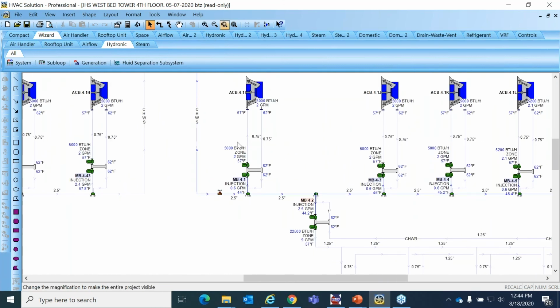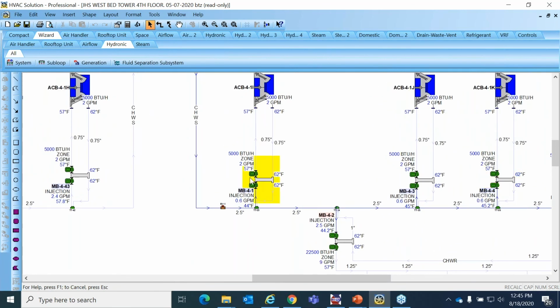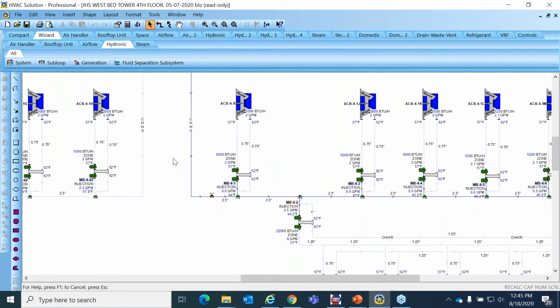The only other thing I would mention, the chill beam controller is looking for input from a wall-mounted temperature humidity sensor as well. It monitors the space temperature and relative humidity. It calculates, based on that data, the dew point temperature. So let's say in this case the dew point temperature is 50 degrees Fahrenheit. Then it will set the injection pump speed in order to maintain some predetermined temperature above the dew point temperature. So if the dew point temperature happens to be 52 degrees, and they want to maintain 5 degrees above, it's going to maintain 57 degrees in the pipe itself. And so that's fundamentally how the low flow mixing block works.